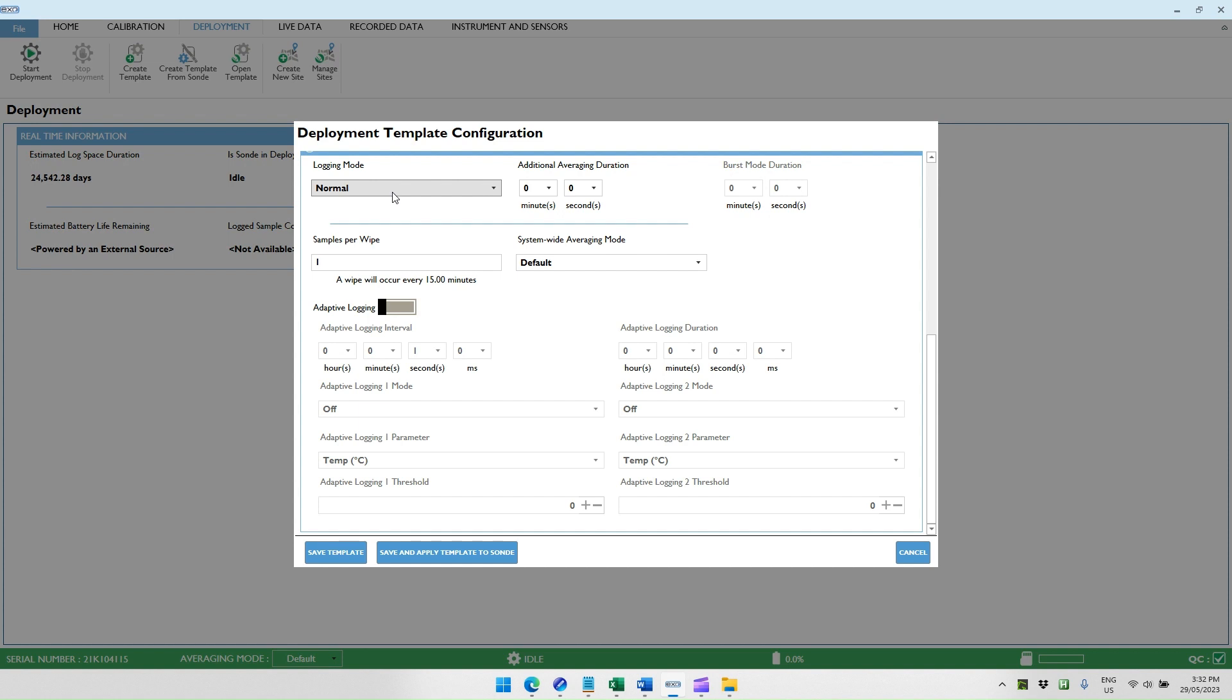However, that can cause a conflict if the sonde is taking a measurement according to its schedule and the AI-1 requests a measurement, which can be a problem if either one is doing a wipe when the other one is requesting a measurement. Because if a wipe is occurring when a measurement is being made, a lot of optical values and conductivity will be erroneous values.